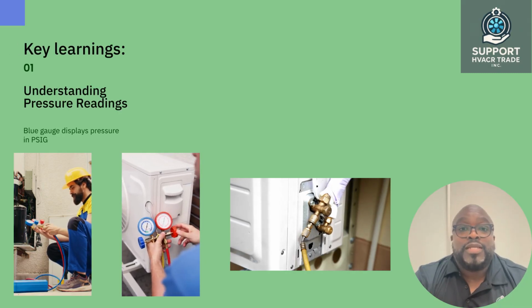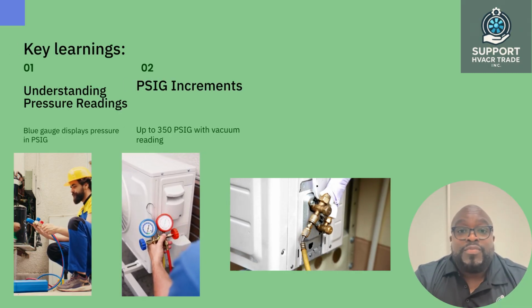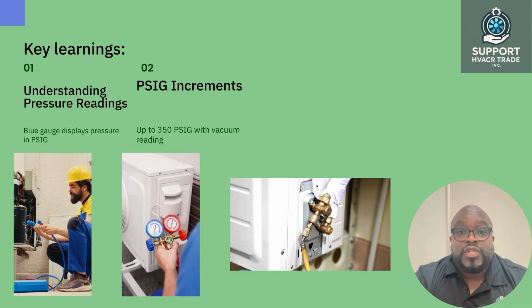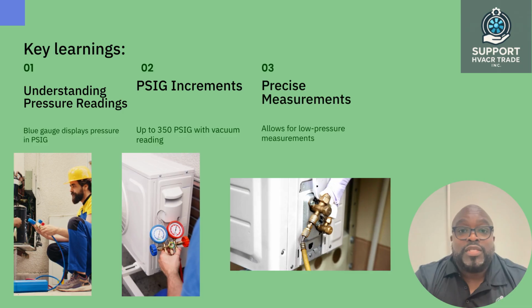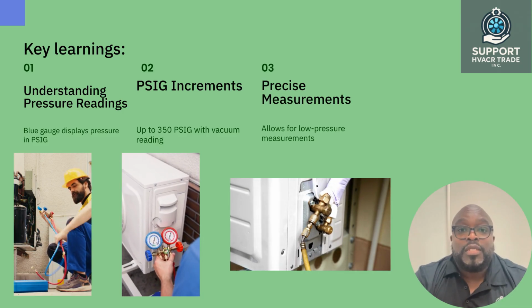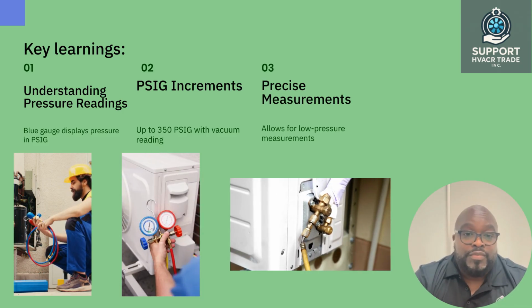Understanding pressure readings on the gauges is vital. It displays pressure in psig increments up to 350 psig, with a vacuum reading in inches of mercury on the low side, allowing for precise low-pressure measurements.